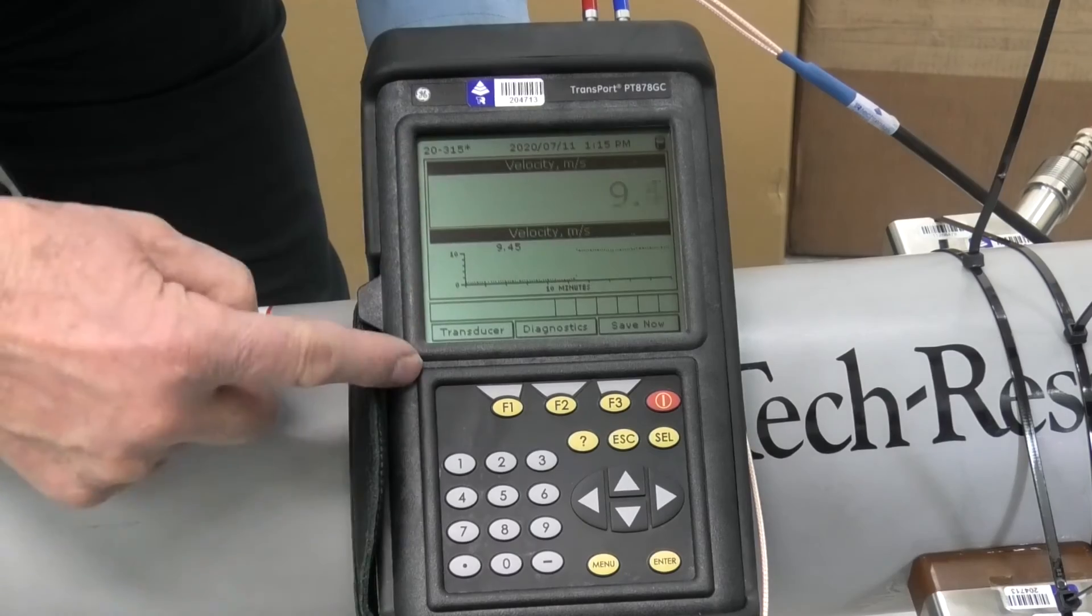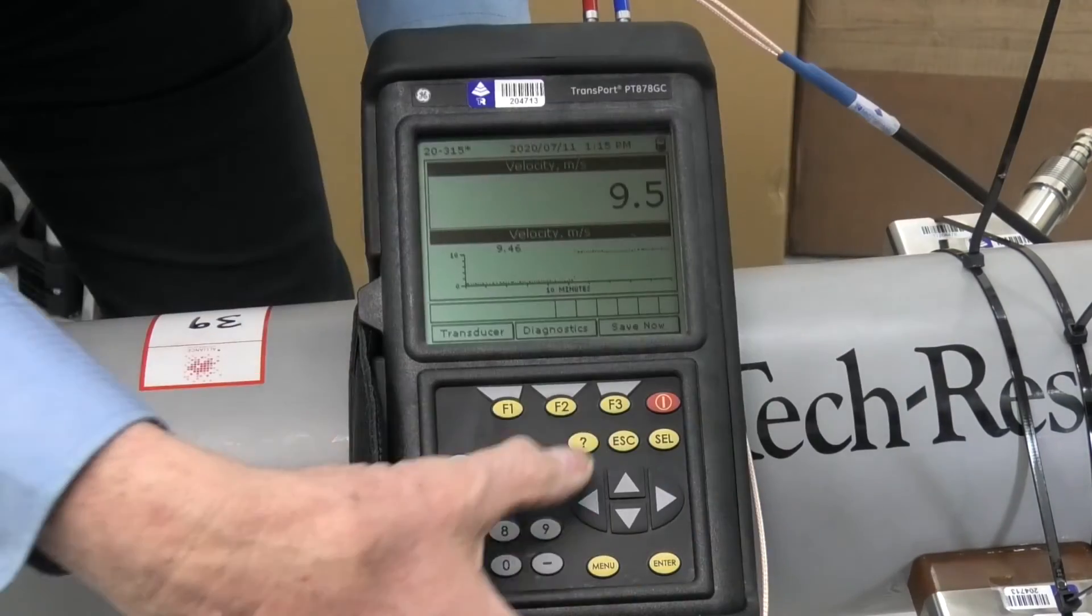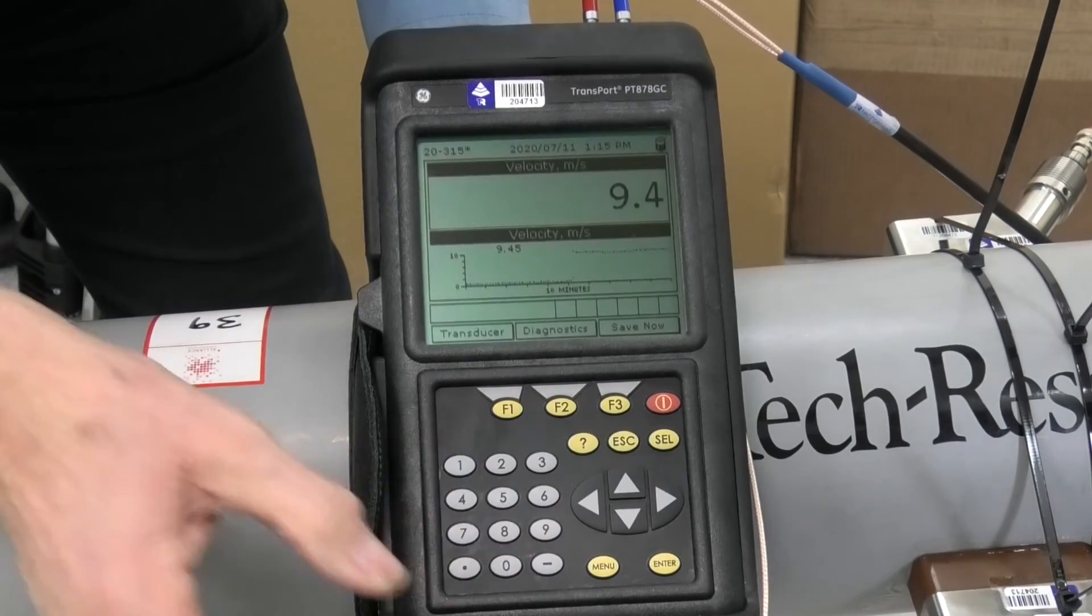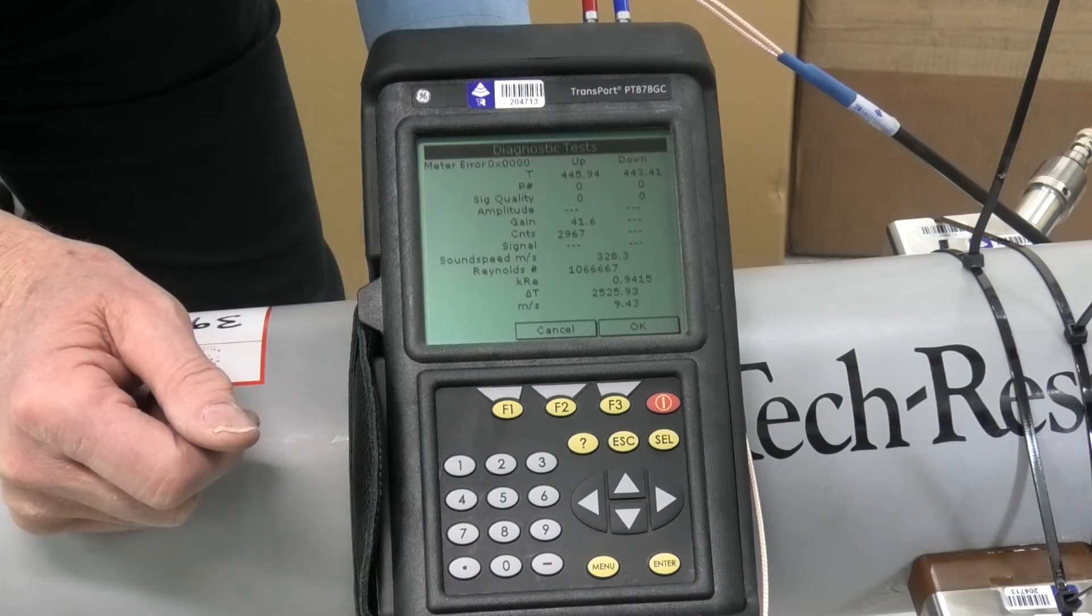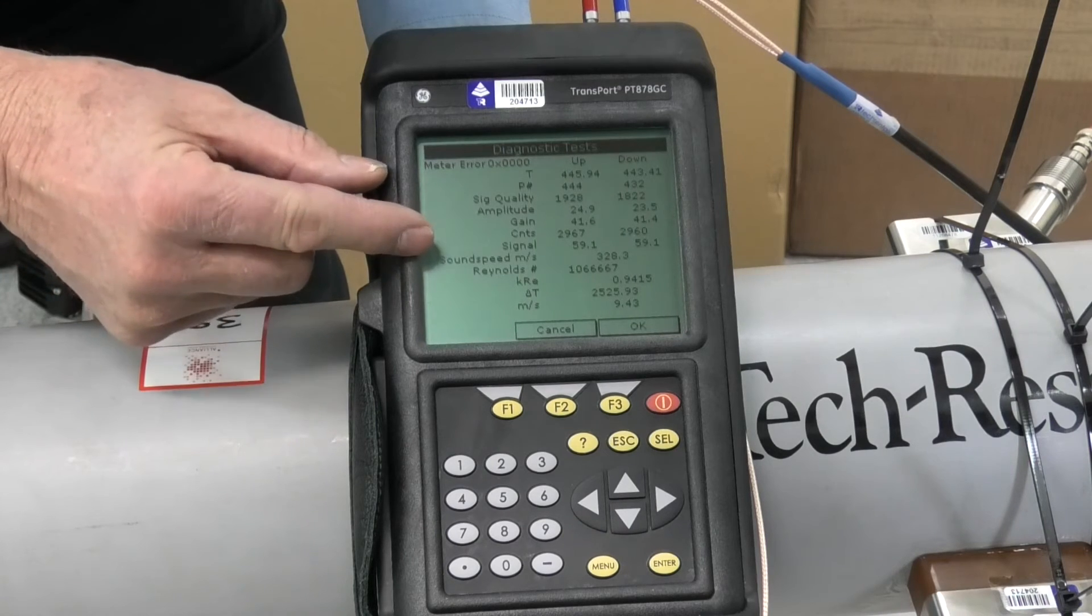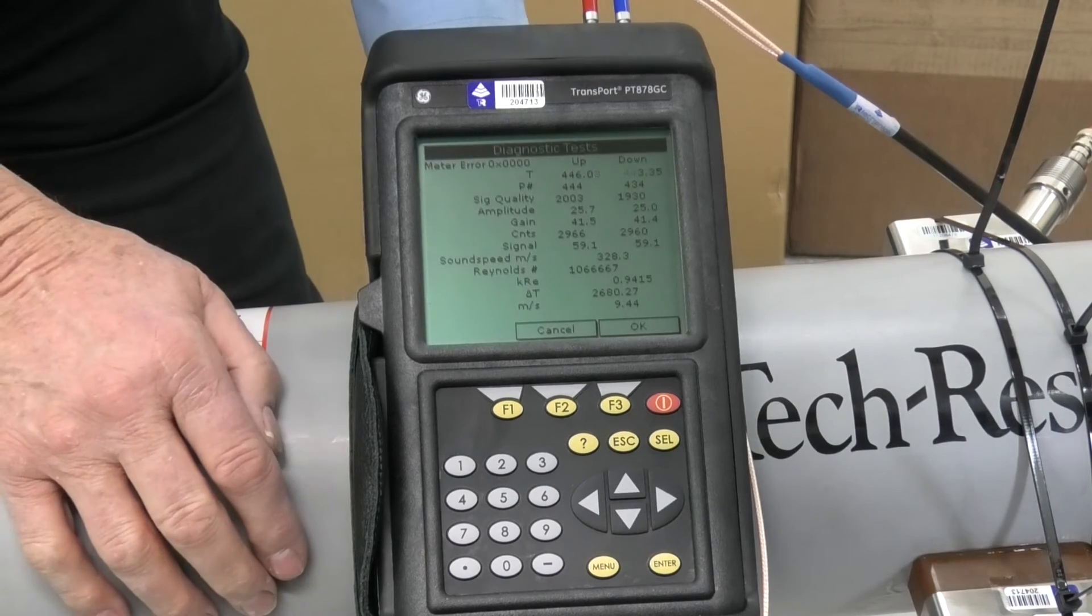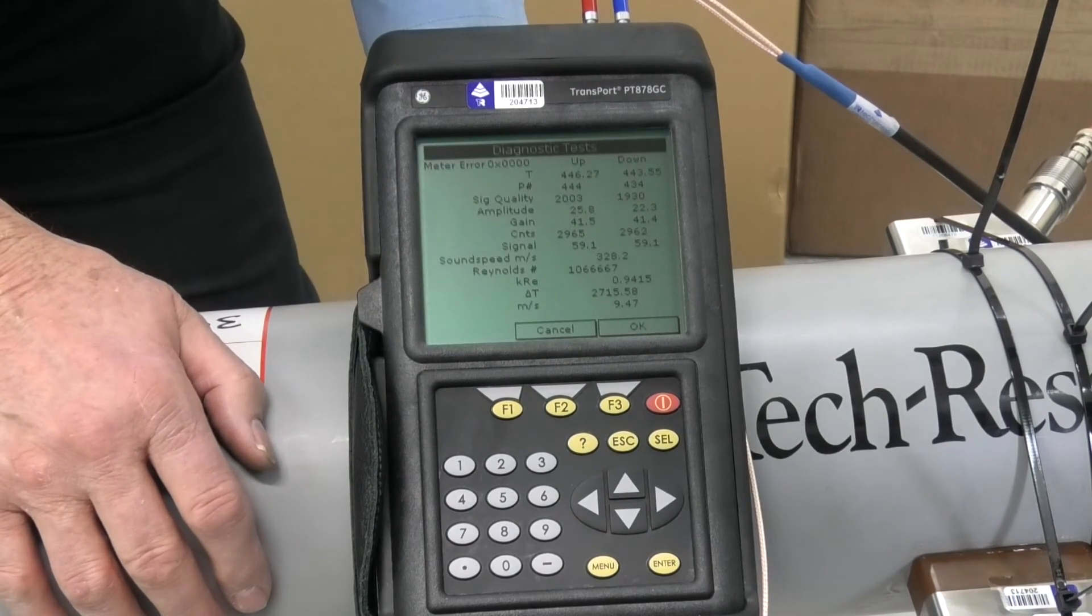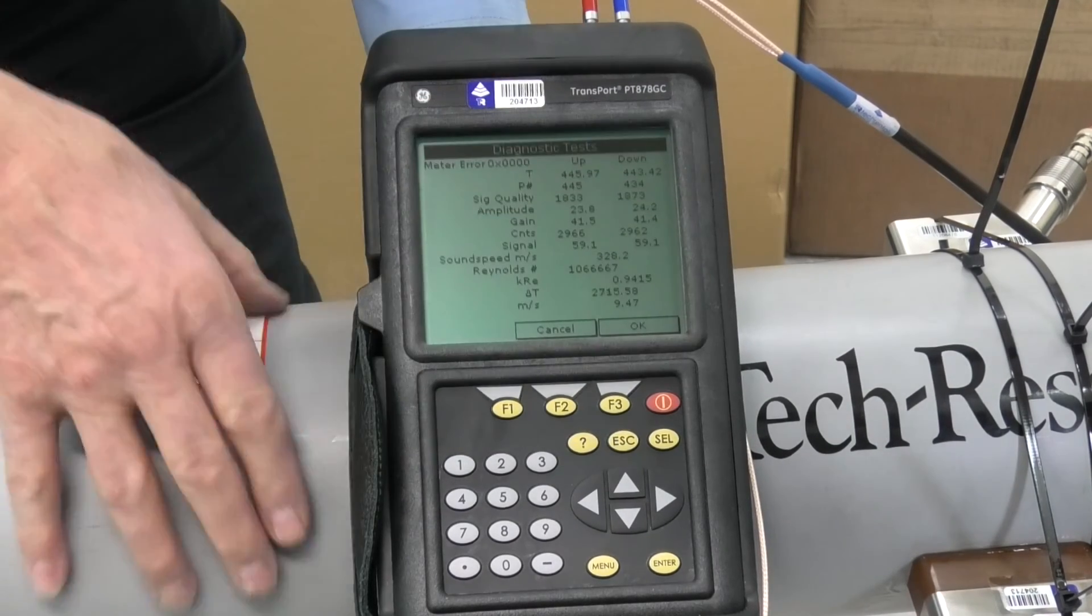Now, one of the things you've got to do when you're using this on compressed air to check whether or not your dampening material here is working, is you've got to hit this diagnostic button here. And we wait, and this brings up the diagnostics. Now, one of the things it brings up is the sound speed. And you've got to make sure the sound speed here is about correct. Now that's 328, measuring 328 metres per second. Sound speed for air, 340 or so, that's close enough.